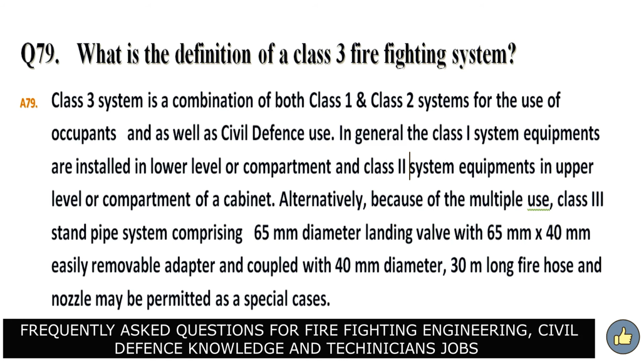Alternatively, because of the multiple use, Class 3 standpipe system comprising 65 mm diameter landing valve with 65 mm into 40 mm easily removable adapter and coupled with 40 mm diameter 30 meter long fire hose and nozzle may be permitted as a special case.